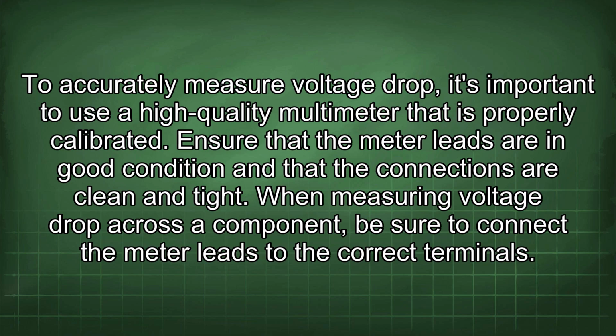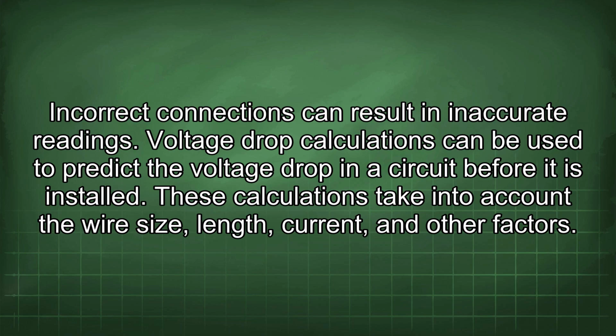To accurately measure voltage drop, it's important to use a high-quality multimeter that is properly calibrated. Ensure that the meter leads are in good condition and that the connections are clean and tight. When measuring voltage drop across a component, be sure to connect the meter leads to the correct terminals. Incorrect connections can result in inaccurate readings.